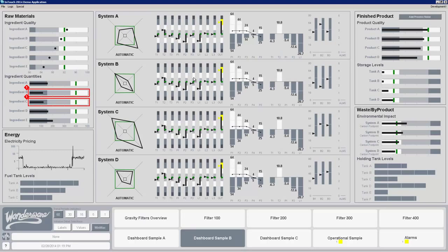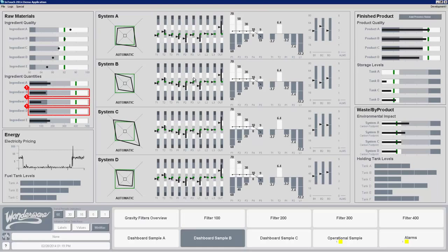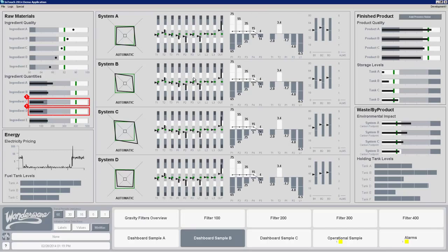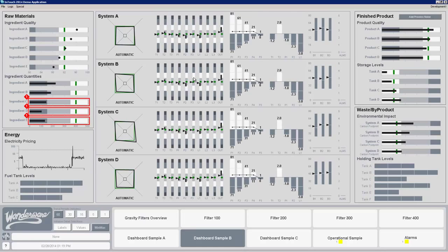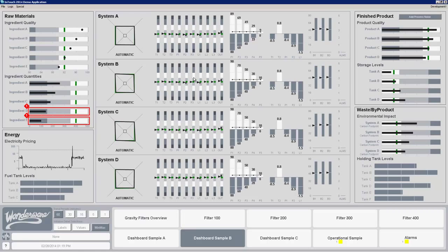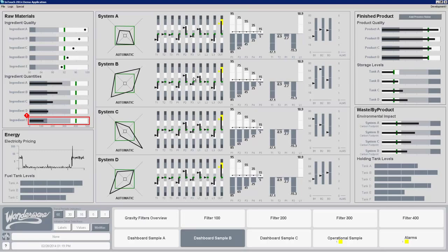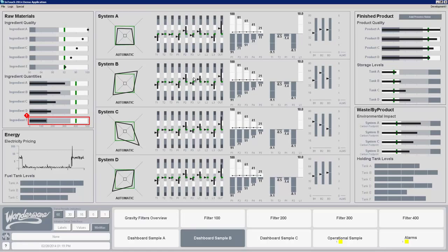But when I started looking at this, I realized that we could look at other organizations in other industries and markets to see how they've addressed this. And very commonly, you've seen tools like business intelligence dashboards. If you look at some of the most contemporary mechanisms used in business intelligence dashboards, I'm showing some of them here on this screen because I felt that there was an absolute parallel for what we were trying to achieve. When I'm looking at my overall process, I don't need to see all the pipes and valves and pumps and motors, and I've seen that done before. My major overview just shows me every piece of equipment in one massive overview screen. That's usually a recipe for disaster when I've seen it done that way.